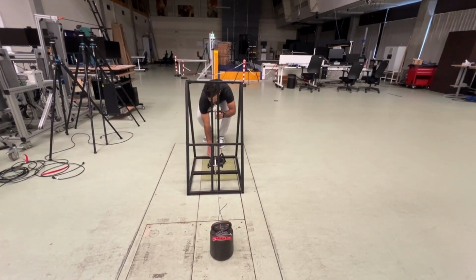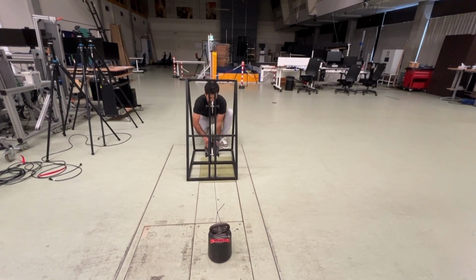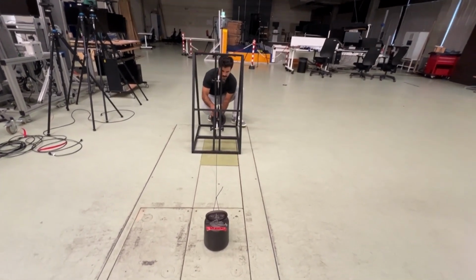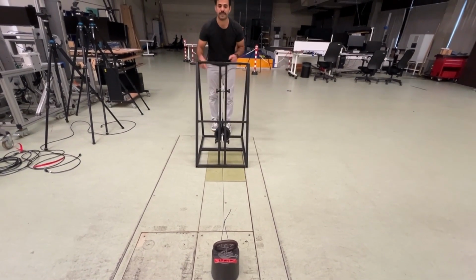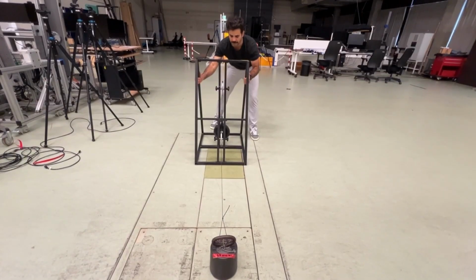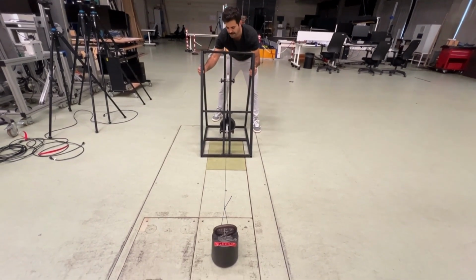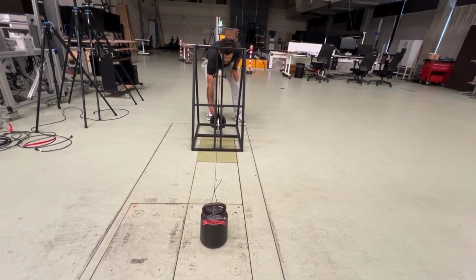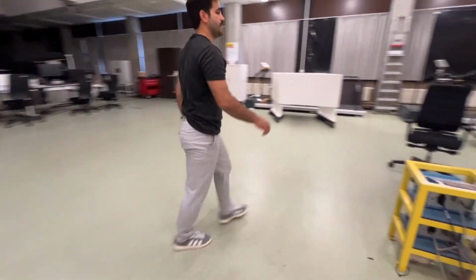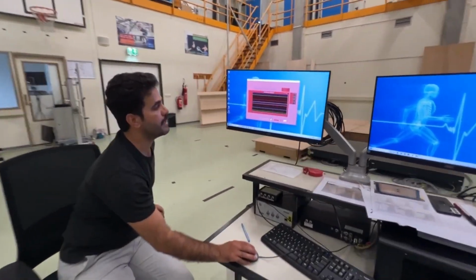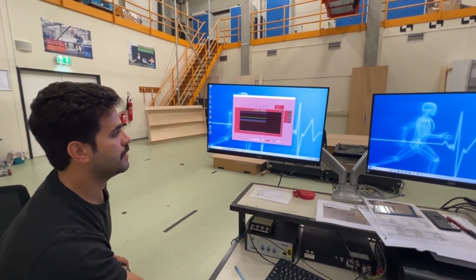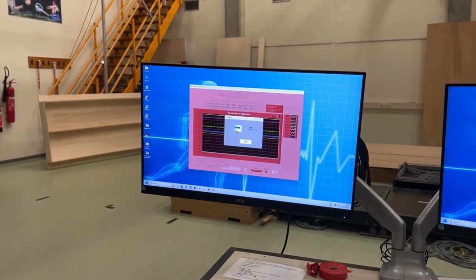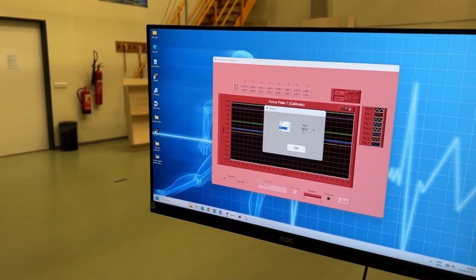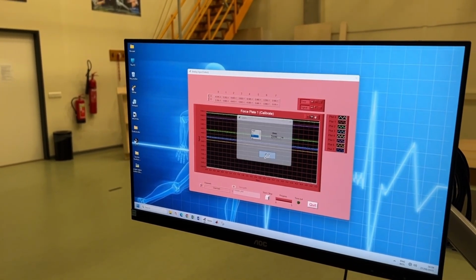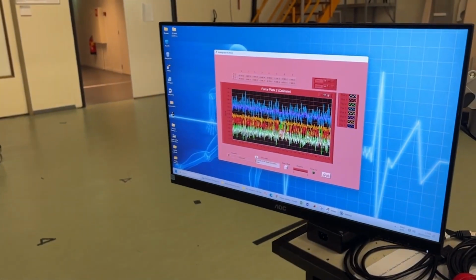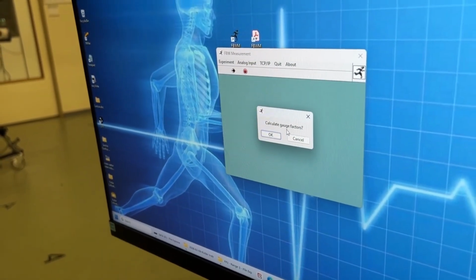I need to bring the frame back, so the weight is hanged on there. Again, make sure that the line of the rope is parallel with the line of the edge of the force plate. You have to go back to the system, click on the start button, and choose the Y direction, and the weight is similar as before, 4.999 kilograms, and we press OK. Now we press the quit button, and to calculate the gauge factors, we press the OK button.